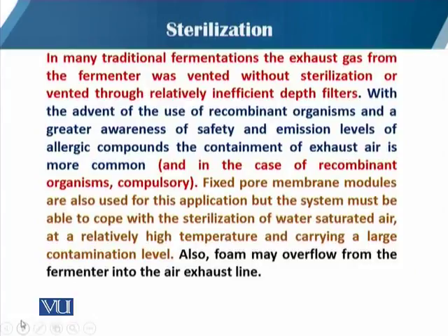So in many traditional fermentations, the exhaust gas from the fermenter was vented without sterilization, or vented through relatively inefficient depth filters. With the advent of the use of recombinant organisms and a greater awareness of safety and the emission levels of allergic compounds, the containment of exhaust air is more common, and in the case of recombinant organisms, it becomes compulsory. So this is the issue when we are dealing with the sterilization of the exhaust air.